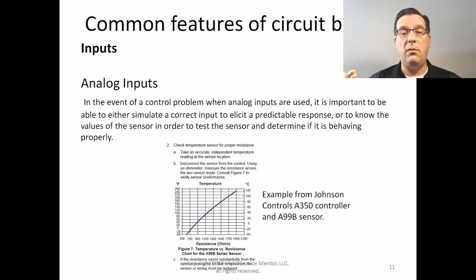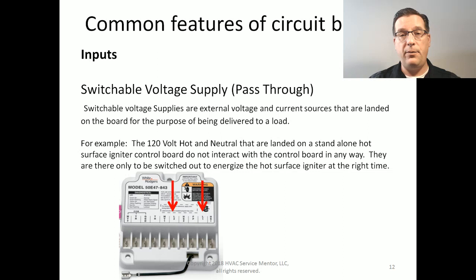Sensor failures are more common than control board failures are. However, a lot of control boards get replaced when there's actually a sensor failure. Some people just go ahead and replace everything. Solves the problem, but not the most efficient way of doing it.